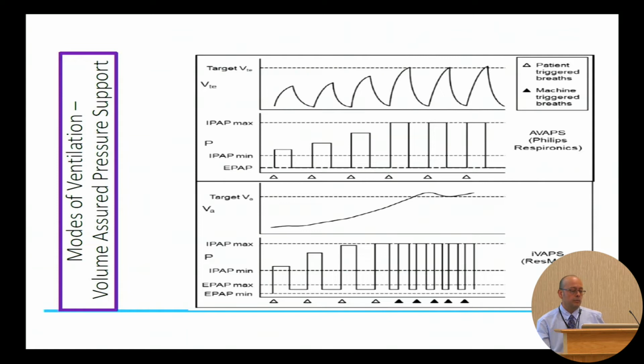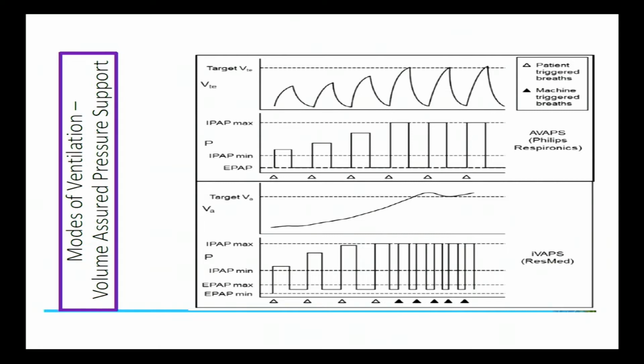This is a graph of what both AVAPS modes are going to do. The one here on the top is the one from Respironics. This device targets tidal volume, and when you do your titration in the sleep lab, you're going to set the target tidal volume based on ideal body weight. And then you're going to have an EPAP that could be fixed or could be APAP. And then you're going to give the device limits. One of the limits is IPAP min and IPAP max.